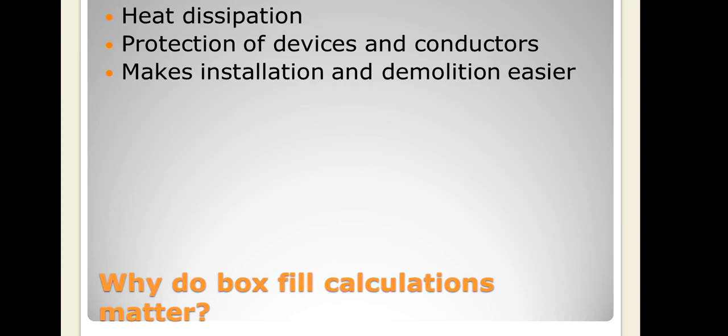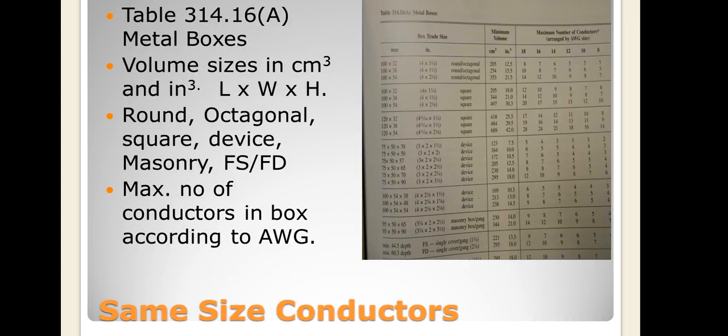Okay, so today's discussion is on box fill calculations. And the primary reason for box fill calculations is to allow for dissipation of heat and to protect the conductors and the devices in the box. Also to make the installation and demolition of the boxes easier.